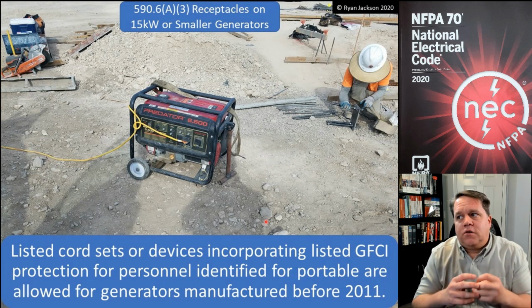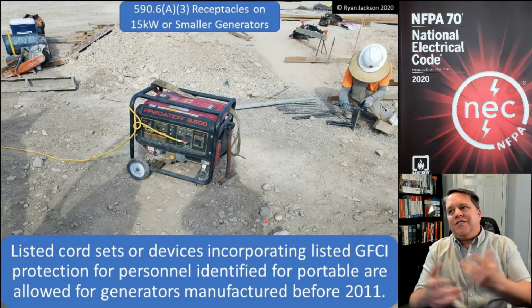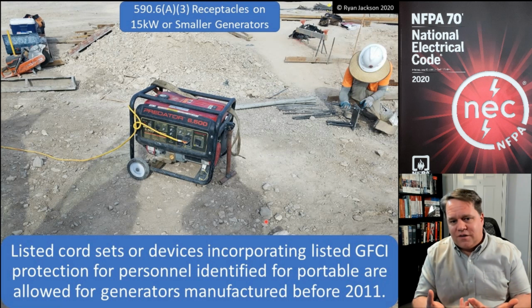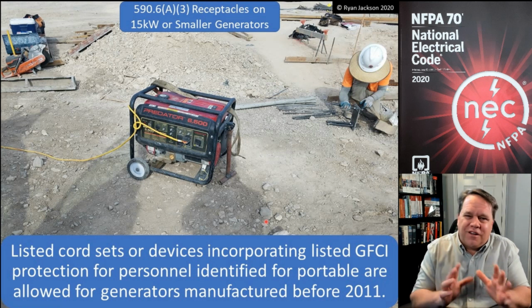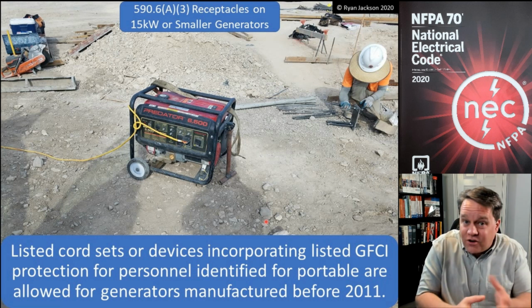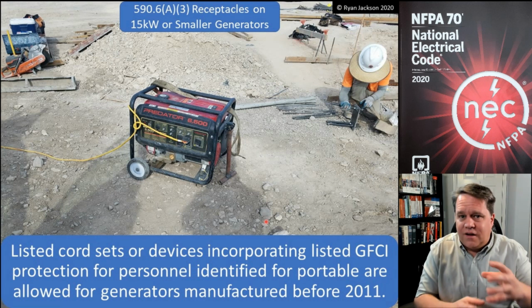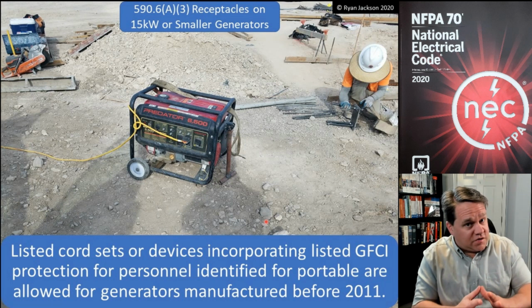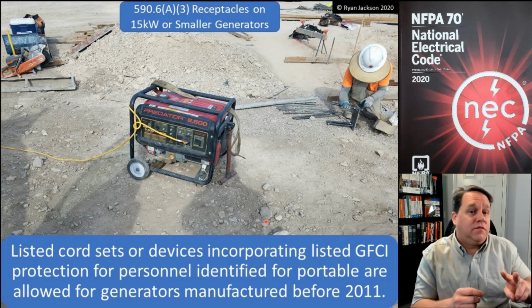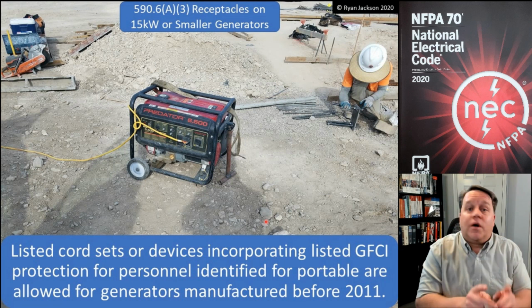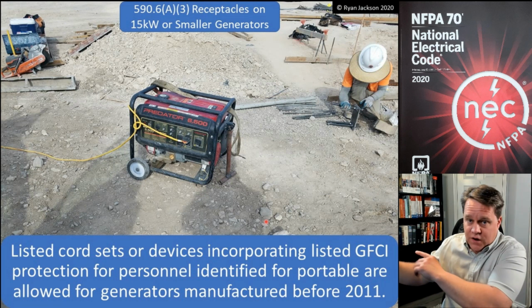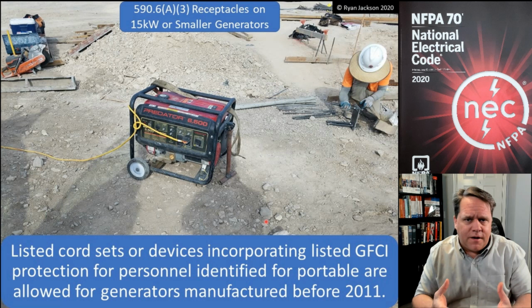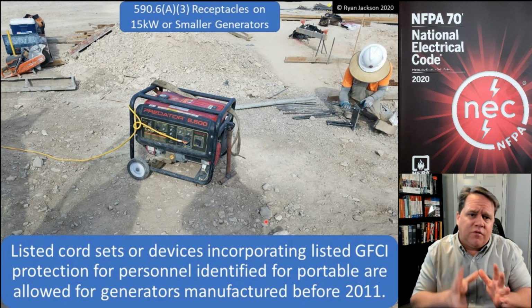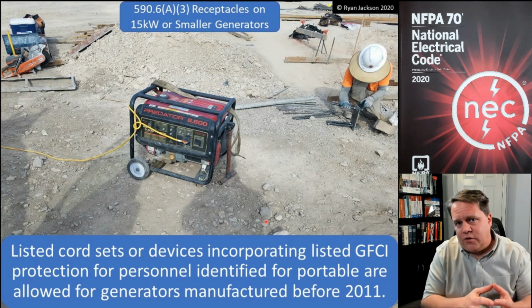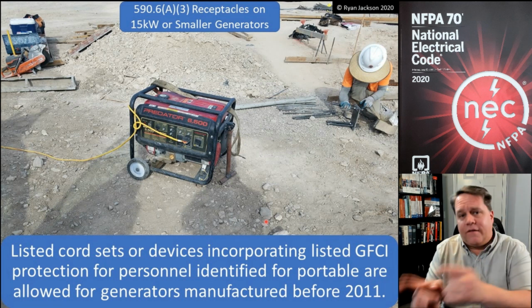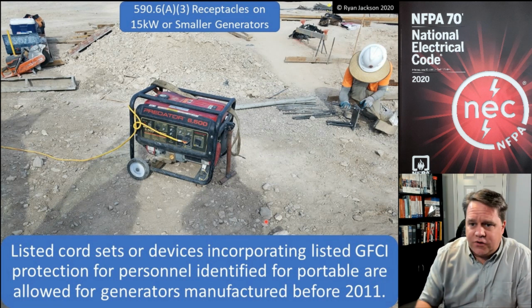And if it's not bonded to the frame of the generator, then a GFCI wouldn't really work, because it's kind of, I don't want to use the wrong terminology, but it's kind of an ungrounded system. And when I say ungrounded system, I'm not talking like a 2-wire house, you know, from 50 years ago. An ungrounded system is something completely different. So back then, before 2011, you didn't really have GFCI protection on portable generators. Sometime after the 2011 code change, it became mandatory.